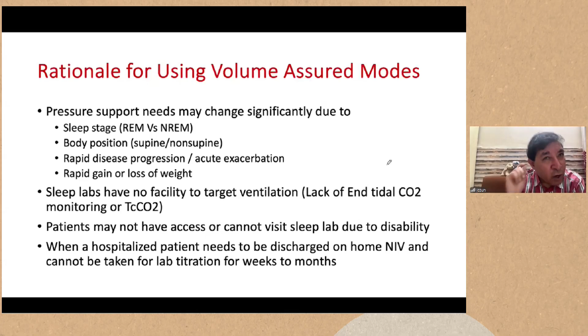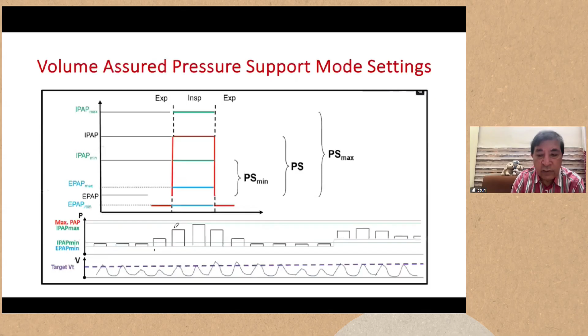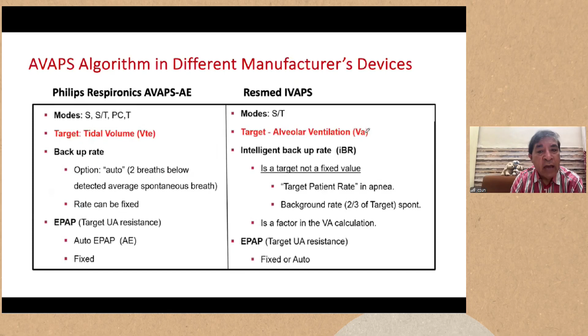So in such situations, you keep the tidal volume constant and then give a pressure support window, so that when there is a fall in tidal volume, the pressure support increases. When there is an increase in tidal volume, the pressure support decreases. This is what is called volume assured, because you keep the tidal volume or the minute ventilation constant and then give a window of pressure support. You can give a pressure support window, the minimum pressure support and the maximum pressure support, and you fix the tidal volume, and this is how it works. Different manufacturers have different algorithms, because Philips uses tidal volume, Resmed uses alveolar ventilation. Accordingly, you can use all these things. I'll not go into the detail.